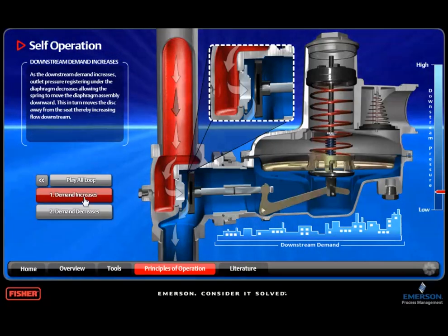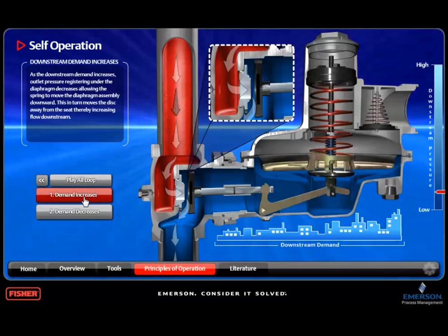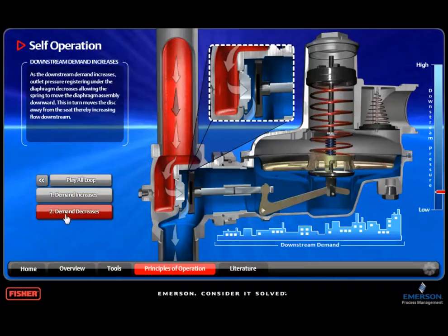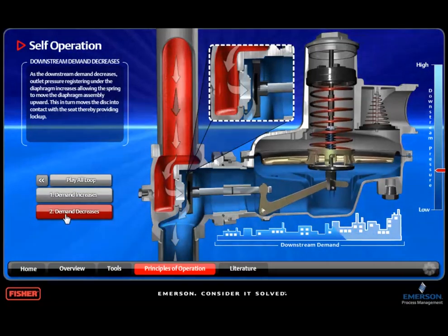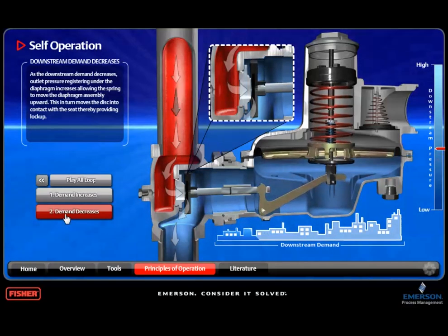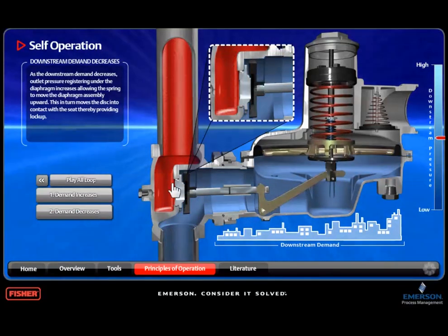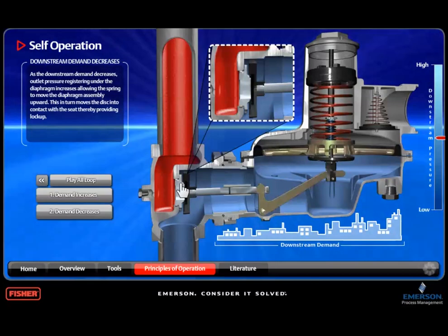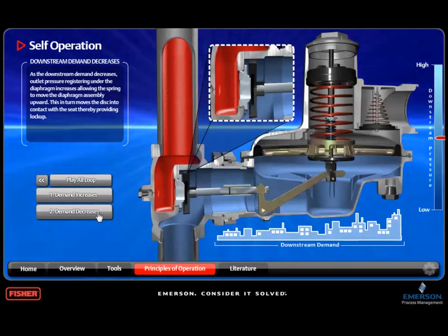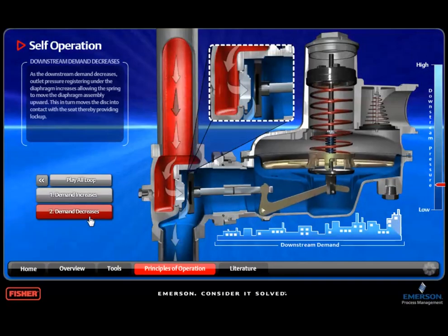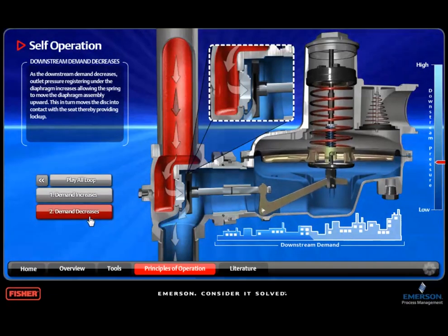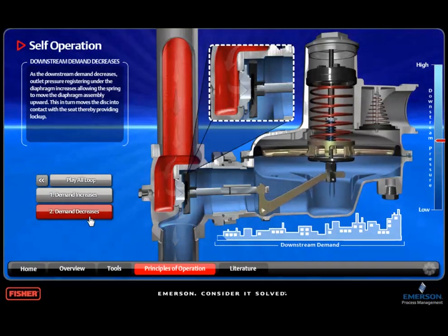Now let's look at what the regulator does when the flow demand from the building's heater decreases. When flow demand decreases, the valve disc needs to move towards the orifice to restrict flow, and the only way that this will happen is for outlet pressure to increase back up to where it was initially. The only reason outlet pressure returned to its initial set point was that the flow demand is again low.